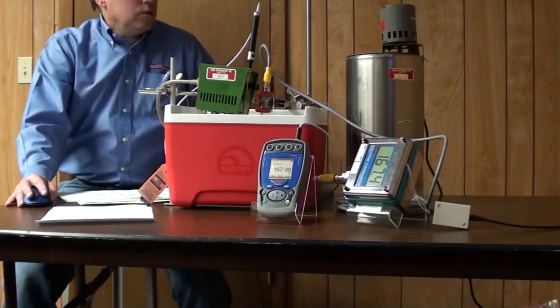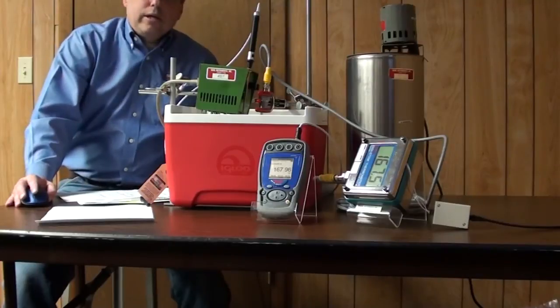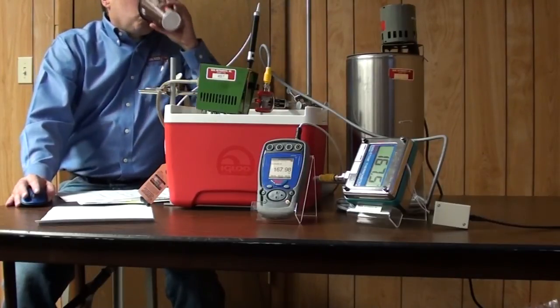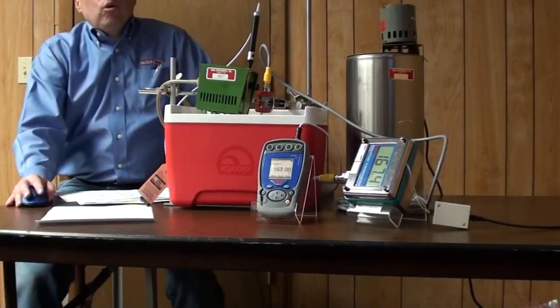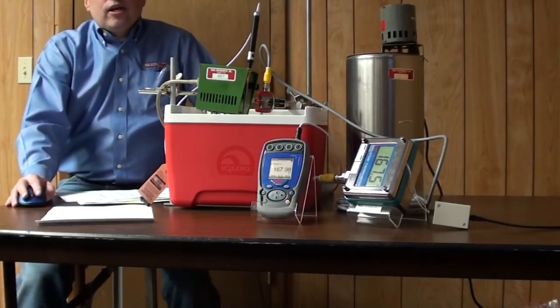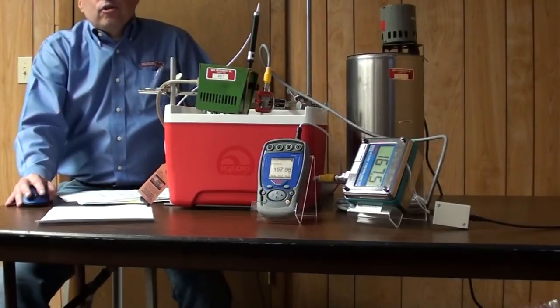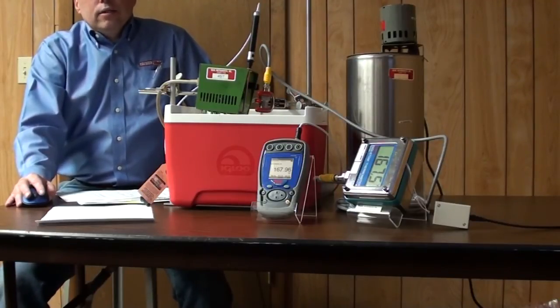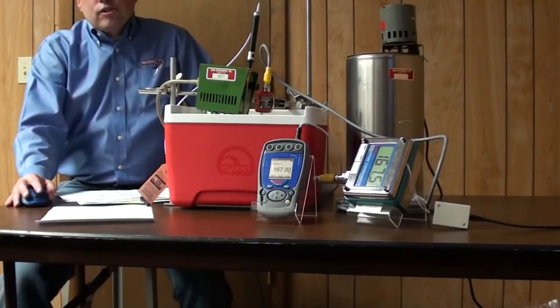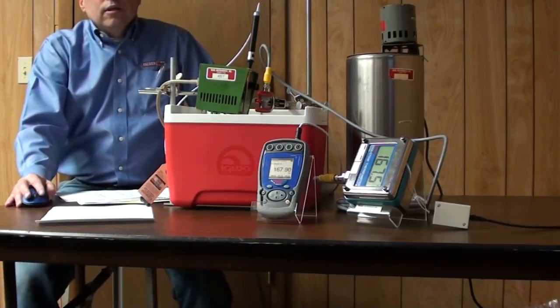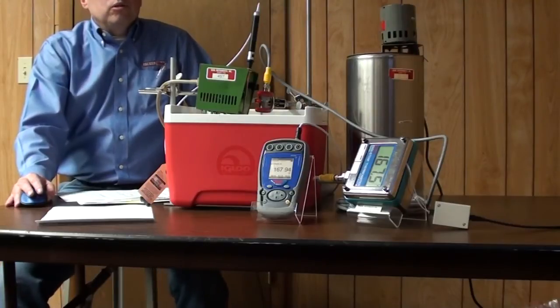You do want to record the temperature and humidity that you're at. If you're doing this in a lab, that's great. I would recommend trying to do this in a temperature controlled area if that's possible. If you're doing it on the factory floor and it's 95 degrees out there, that may affect your accuracy due to ambient temperature. If it's calibrated at 95 degrees, then if you're using that thing now in the wintertime at a much lower temperature, you will have more of an effect of ambient temperature on it.